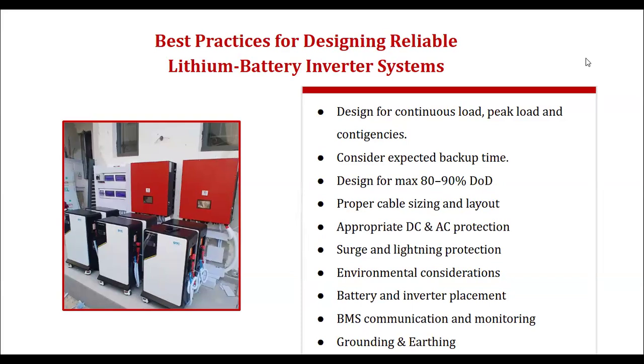Environmental consideration: don't install your system where there is drainage, water, or high temperature like in the kitchen, where there are oil fumes - consider all this. They need to stay cool and away from moisture. Don't assume because a battery is labeled IP64 you can put it where water or rain falls on it, or where the inverter gets exposed. No - we need to be conscious of all this.